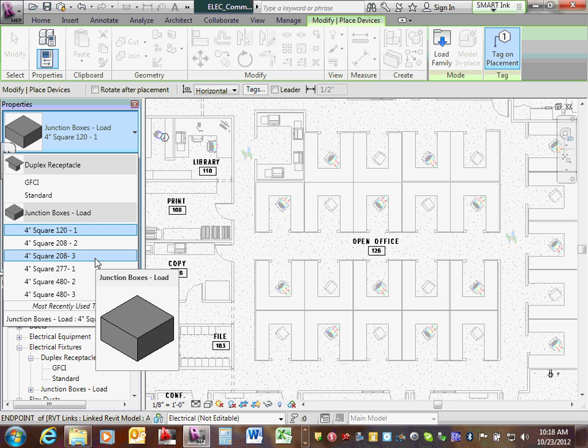Why 208? 208-3, guys, it will give you the voltage phase to phase at 208, but 3 circuits, and each of the 3 circuits is 120. Can I have thumbs up? These are called 208-3, meaning it's really the voltage to ground where the neutral is 120, and phase to phase is 208, which is typical in a 208/120 system.